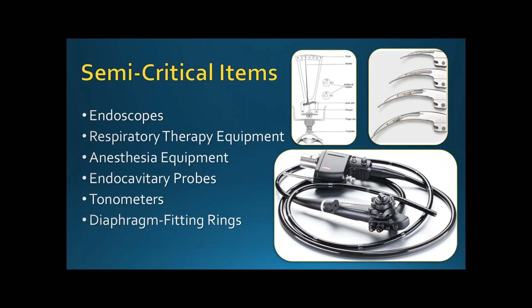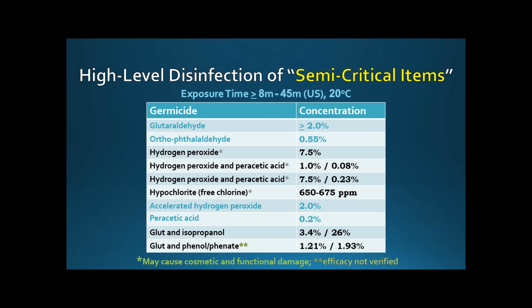So for high-level disinfection, there's multiple different disinfectants that you can use. The most common ones are your glutaraldehyde, your OPAs, your accelerated hydrogen peroxide, and your peracetic acid. And they all have different exposure times and different temperatures that they must be used at to perform high-level disinfection appropriately. So you want to make sure that you read the IFU, pick up and read that bottle to know exactly what is required when it comes to length of exposure time, how to do rinses, all that stuff. But this is going to be your most common list of different disinfectants for high-level disinfection.